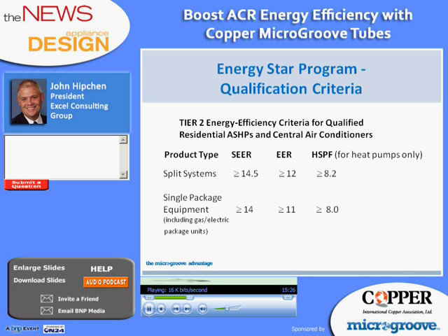Some manufacturers market individual products or even portions of their product line that meet the ENERGY STAR criteria. To qualify for the ENERGY STAR certification, products have to be about 10% more efficient than the minimum federal energy standard. And here we see the current Tier 2 ENERGY STAR specs that took effect on January 1st, 2009. Note the EER qualifications in the ENERGY STAR program. We'll be looking soon at performance data from various designs, and an EER of 12 gives us a reference point to remember.